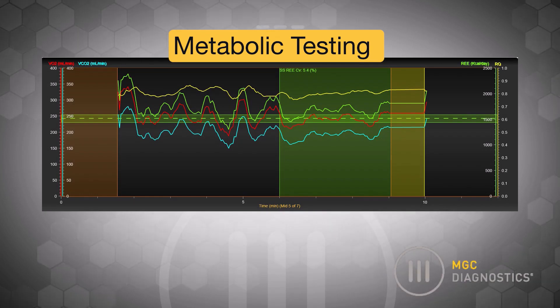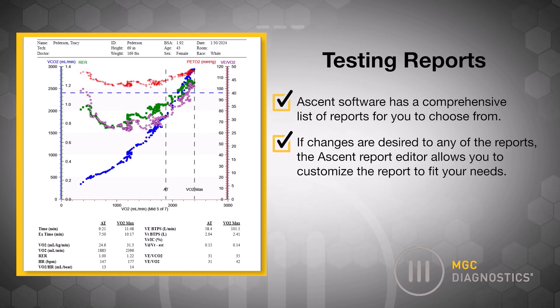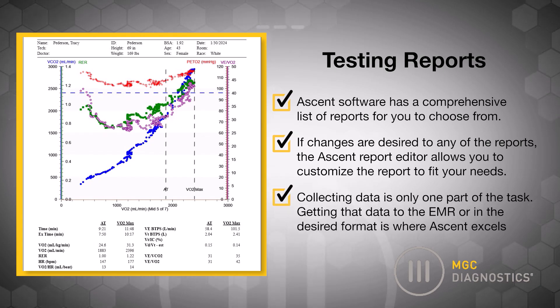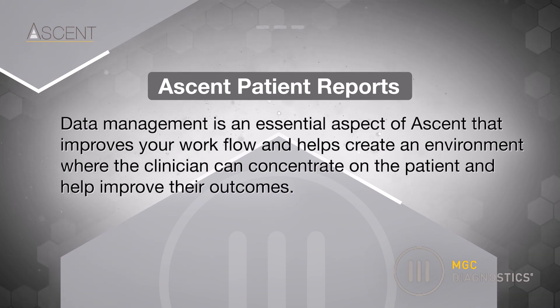Metabolic testing gives you all of the great features of exercise testing in order to collect data on spontaneously breathing patients. And if data collection is interrupted by external forces, such as someone walking in the room, the software gives you the ability to exclude data that doesn't meet your steady-state criteria. When testing is complete, Ascent software has a comprehensive list of reports for you to choose from. If changes are desired, the Ascent report editor allows you to customize the report to fit your needs. Getting that data to the EMR or in the desired format is where Ascent excels. Data management is an essential aspect of Ascent that improves your workflow and helps create an environment where the clinician can concentrate on the patient and help improve their outcomes.